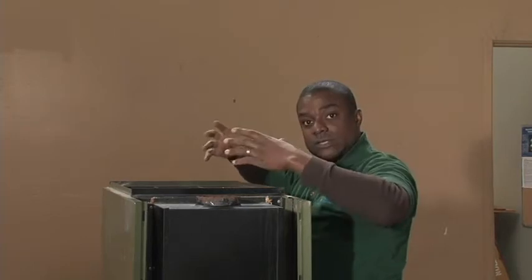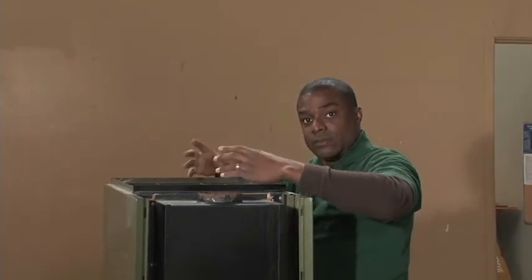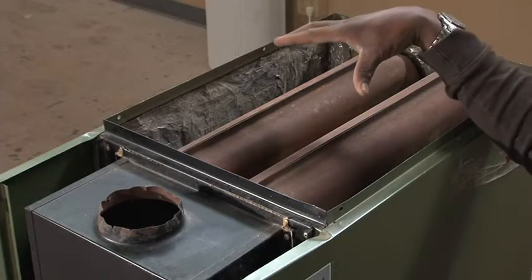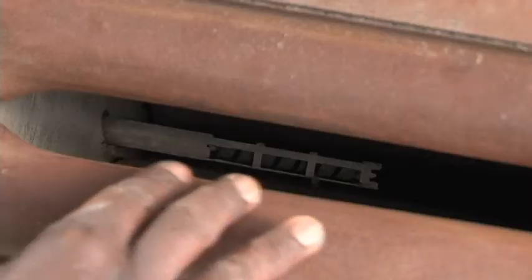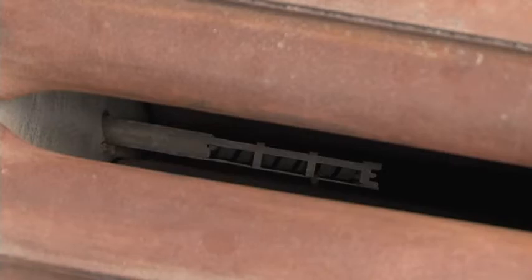On this furnace, the supply side is on the top side of the furnace. So the ductwork that supplies heat to the rest of the house, that's called the trunk line. It would go up here. Connecting to the trunk line, we have a plenum. That plenum then connects to the top of the AC coil, and the AC coil then sits right on top of our furnace. Inside of our furnace, we have a couple of heat exchangers. And if we look down in between these heat exchangers, we see a probe sticking out. We're going to talk about that in a minute.